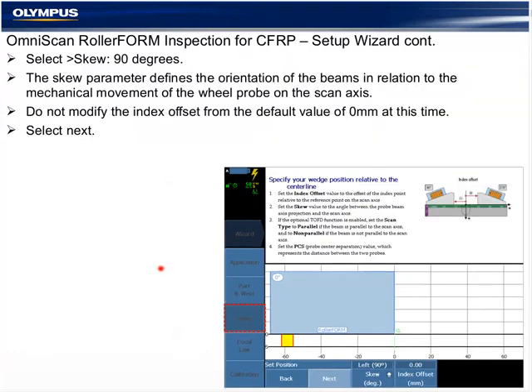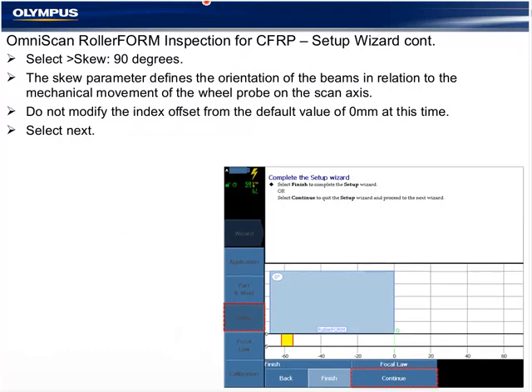Continuing on in the setup wizard, we select a skew of 90 degrees. The skew represents the beam orientation in relationship to the mechanical movement, which is also the scan axis or blue ruler, and should be left at 90 degrees. And our index offset for now is going to be left at 0. We'll talk a little bit more about the index offset when we get into inspection preparation.